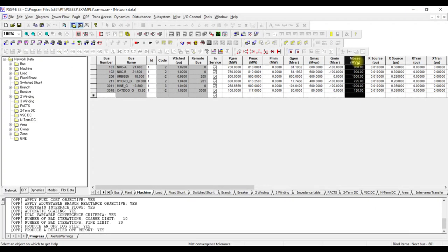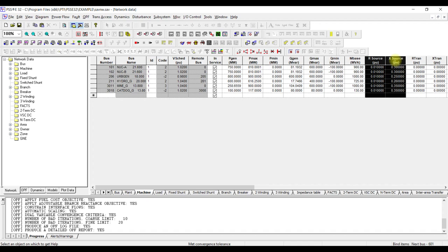Similarly, the MVA base — this is the MVA rating of the generator — can be modeled here. There are also R source and X source values, which we discussed in the very first lecture. These values are very important when it comes to short-circuit analysis. Even if you do not model them for load flow analysis, nothing will happen, but when you are performing short-circuit analysis these values become critical.